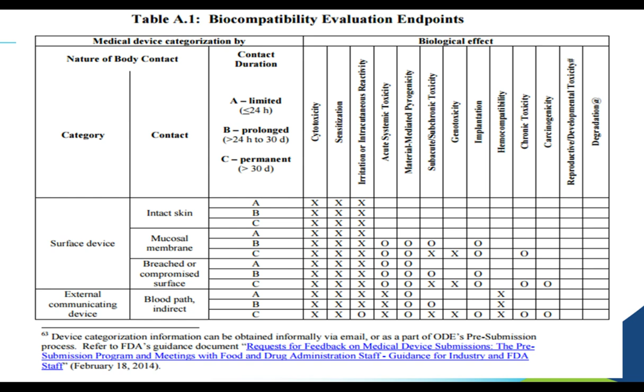Once we've identified those things, we look at the biological effects that are listed here in tabular form. You can see that cytotoxicity, sensitization, and irritation testing are required for every single medical device on the market, either testing or some sort of risk mitigation step. That's why irritation testing is really a hot topic. Out of these three tests, cytotoxicity currently is the only in vitro method that is available and approved. So what we're moving towards is an in vitro method for irritation. This has a significant impact in the medical device industry and especially in animal welfare.